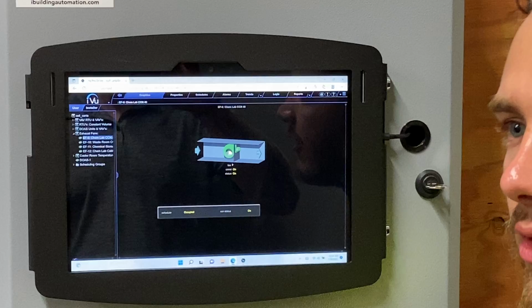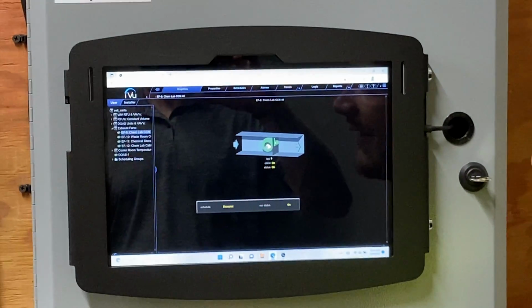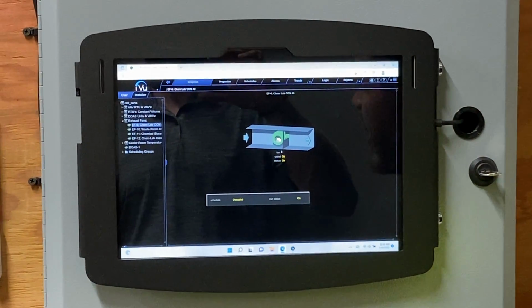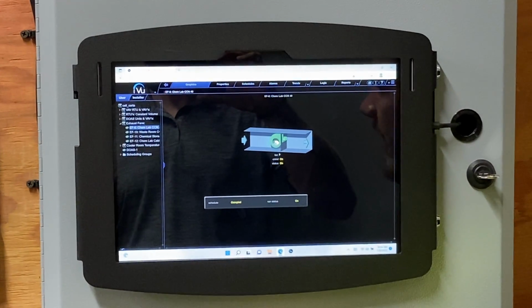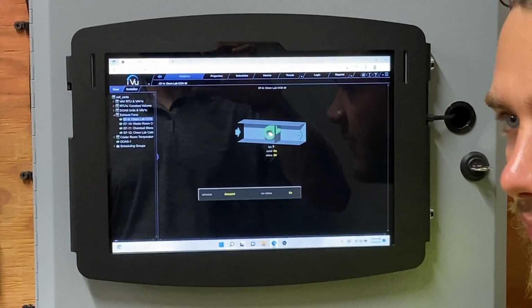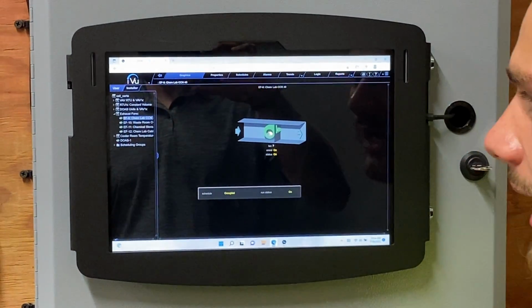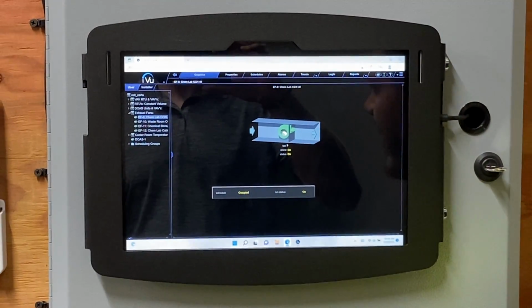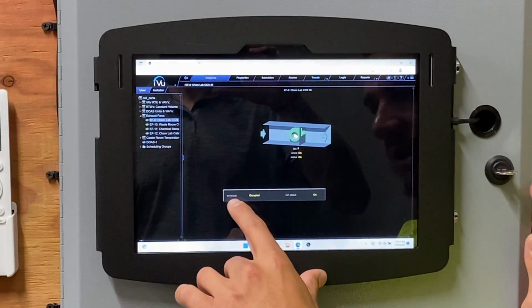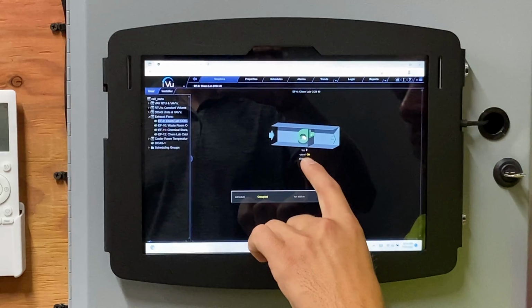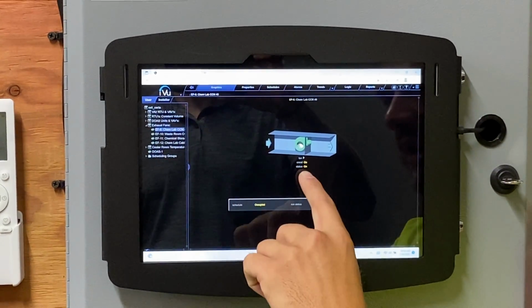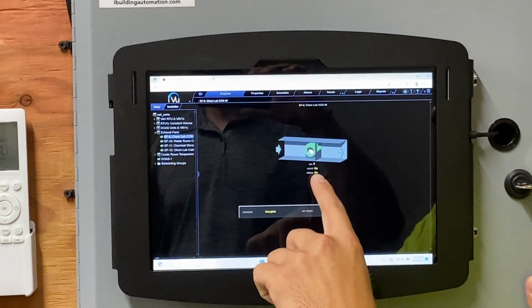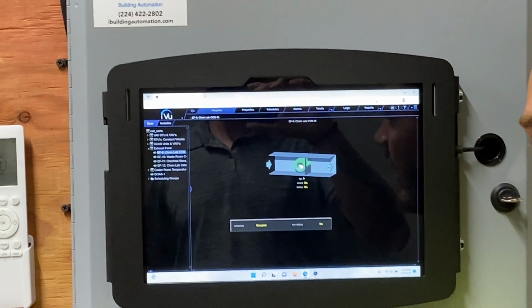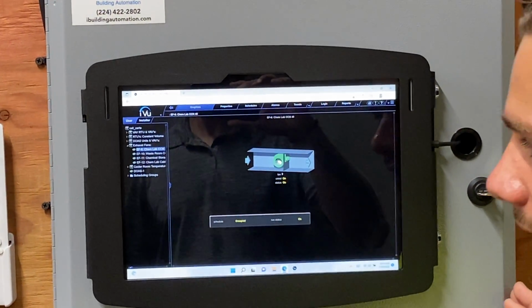The exhaust fans now are running off of a schedule. At the end of this, we'll actually configure a schedule here, and I'll do it in front of you guys. You let me know what days are operational, Monday to Sunday, but right now we have them as 24/7 operation. So my schedule here says occupied. My command for my fan to be on is on, and my actual status transducer is reading on as well. Then our graphic here is spinning, showing the exhaust fans running.